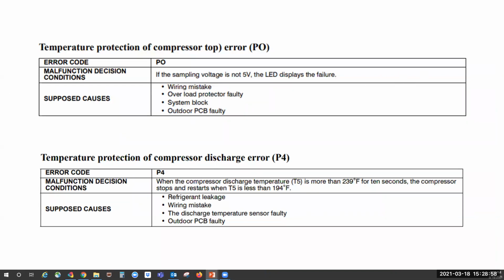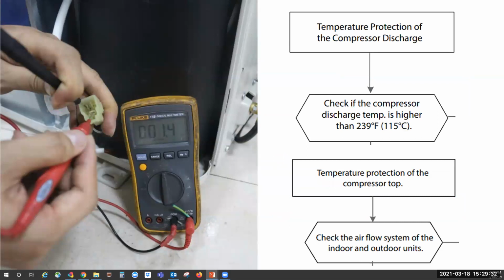Now we're getting to P0 and P4 codes. This can also be caused by a bad IPM board or a bad compressor. You want to check the board, check the compressor, check the ground. There are some more items to check, but these are the main ones we check first, because they're usually the ones that take the brunt of the damage. Remember to always check for loose connections, possible burnt wires, mice chewing through them. When checking the compressor, you can check the U, V and W for DC volts, and you're going to refer to your service manual for the correct readings. We'll get into the compressor checking here in just a moment.